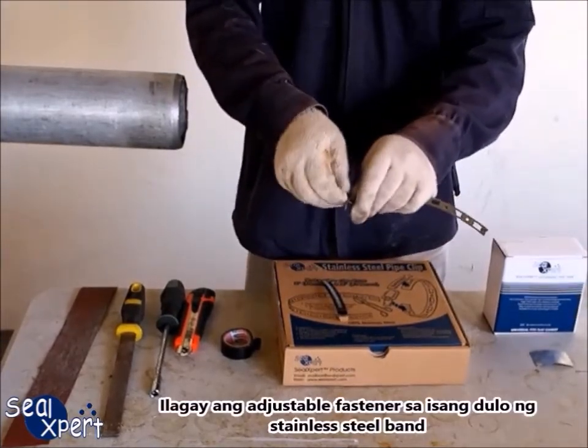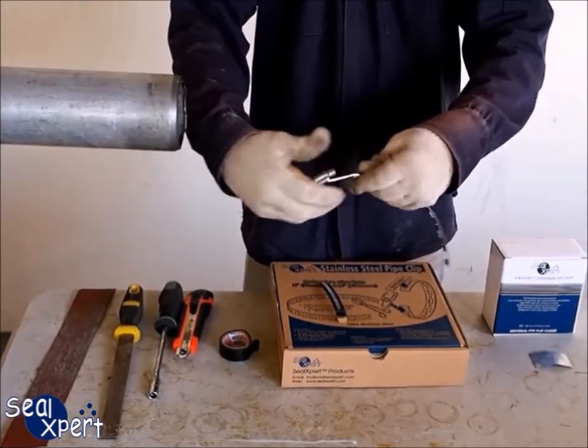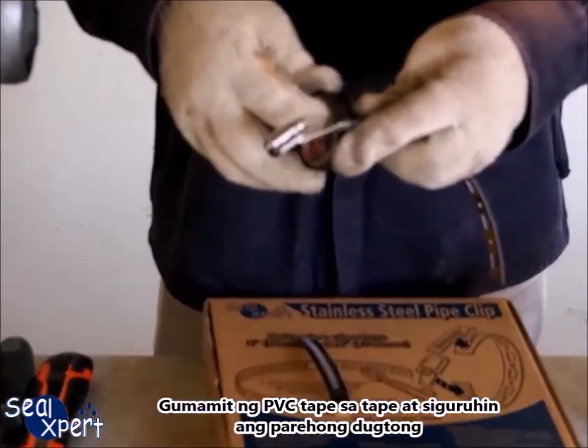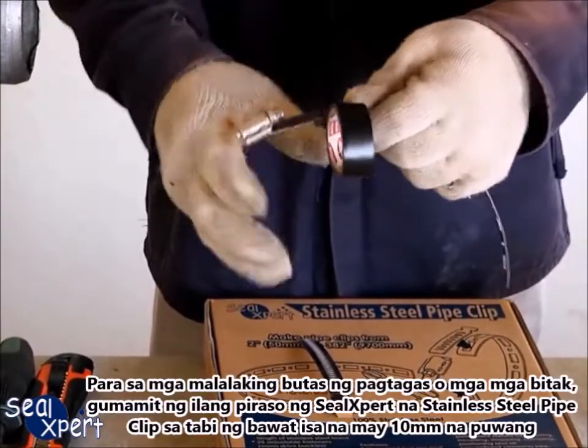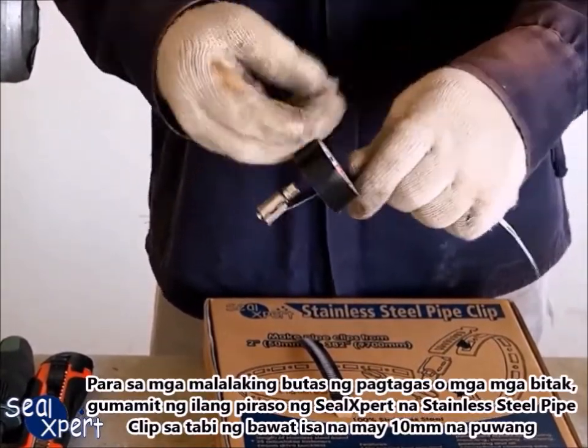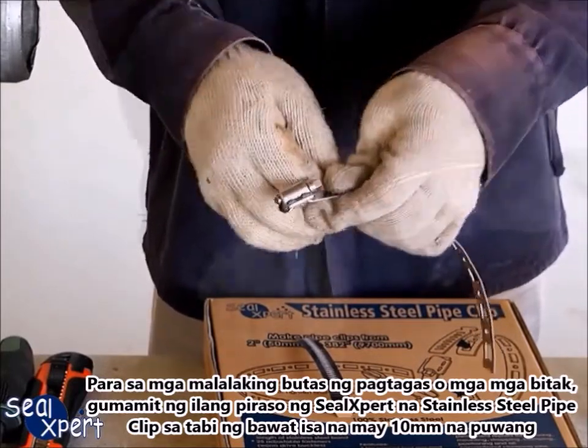Slot the end of the adjustable fasteners one to each end of the stainless steel band. Use PVC tape to tape and secure both joints. For large leak holes or longitudinal cracks, use several strips of SealXpert STAINLESS STEEL PIPE CLIP alongside each other with a 10 mm gap.